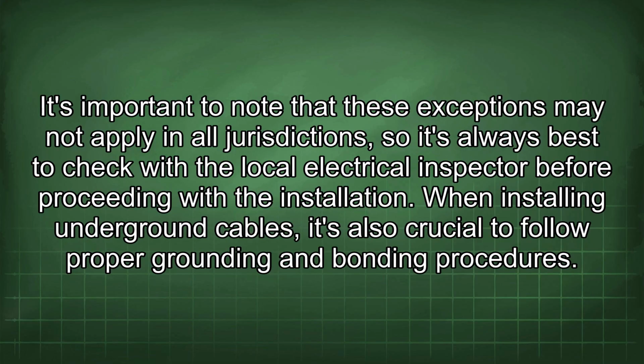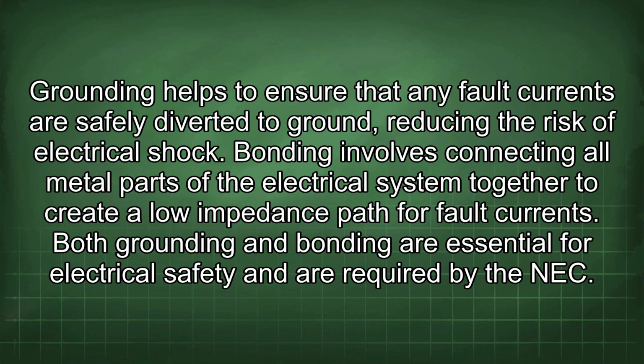When installing underground cables, it's also crucial to follow proper grounding and bonding procedures. Grounding helps to ensure that any fault currents are safely diverted to ground, reducing the risk of electrical shock. Bonding involves connecting all metal parts of the electrical system together to create a low impedance path for fault currents. Both grounding and bonding are essential for electrical safety and are required by the NEC.